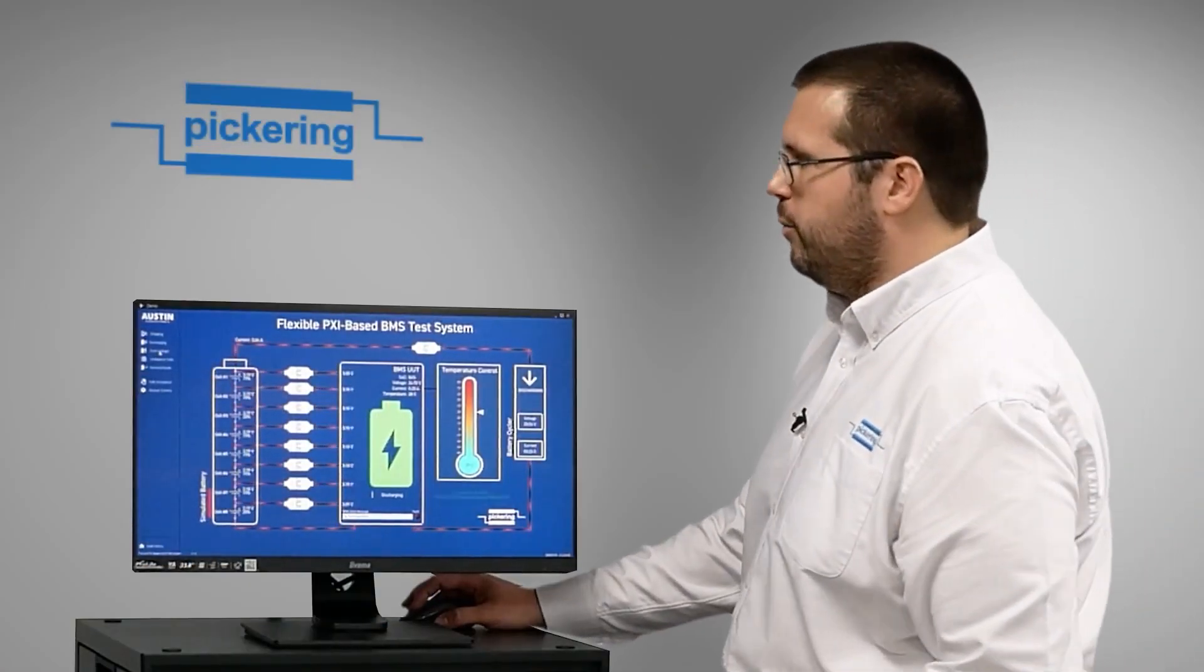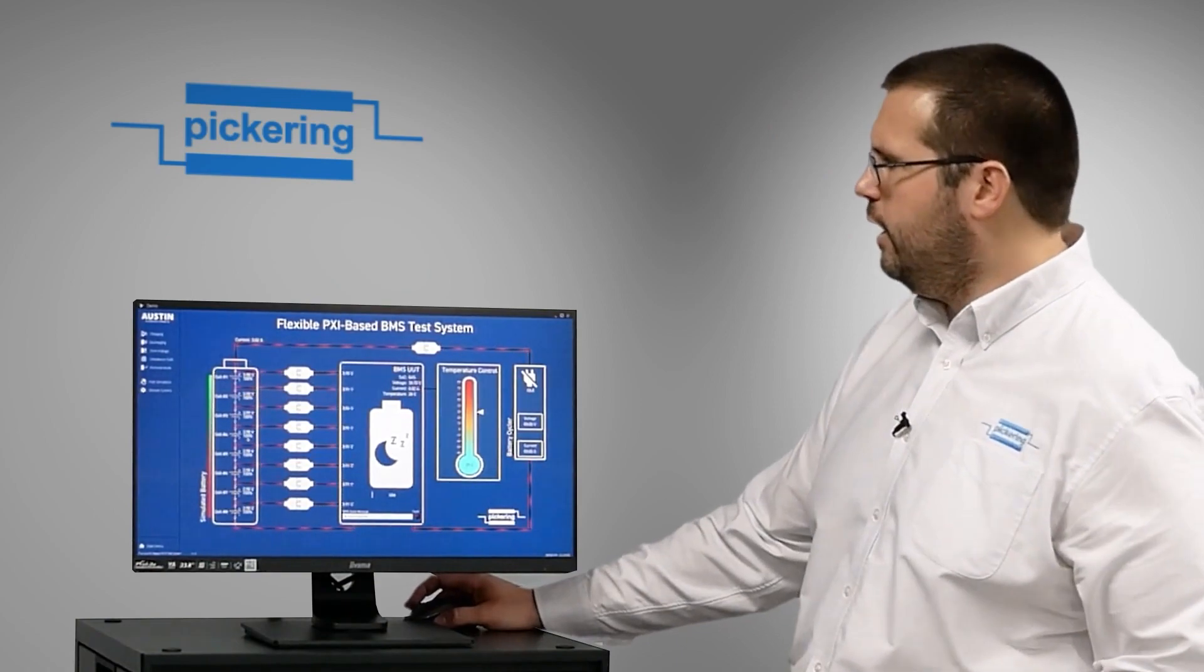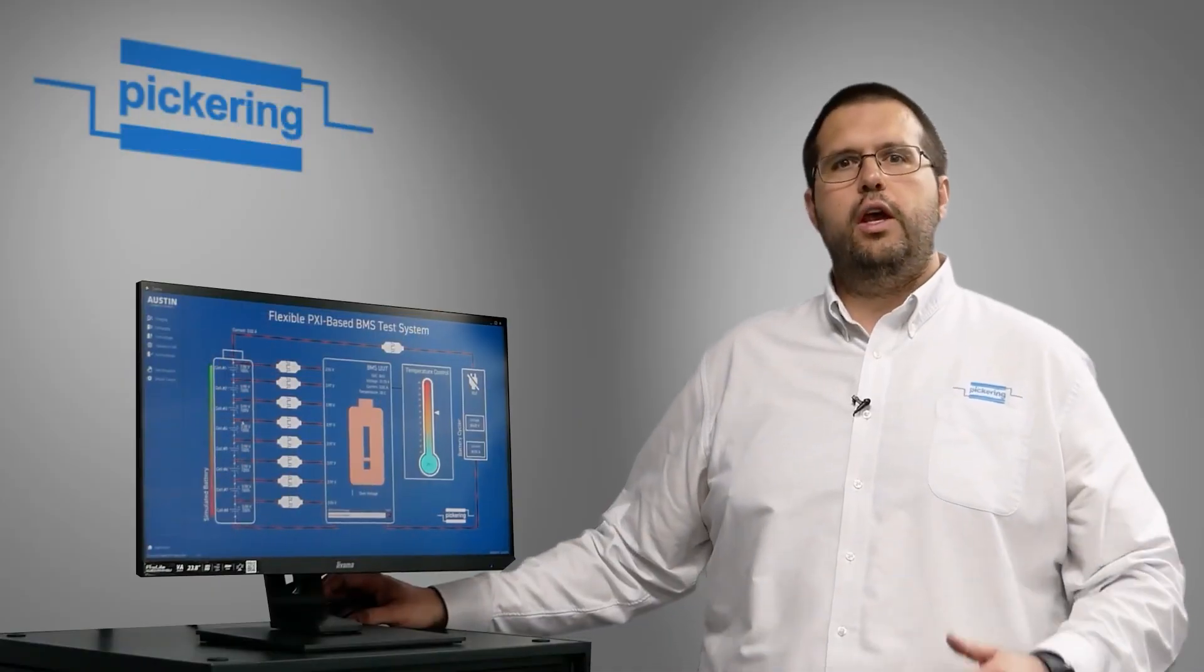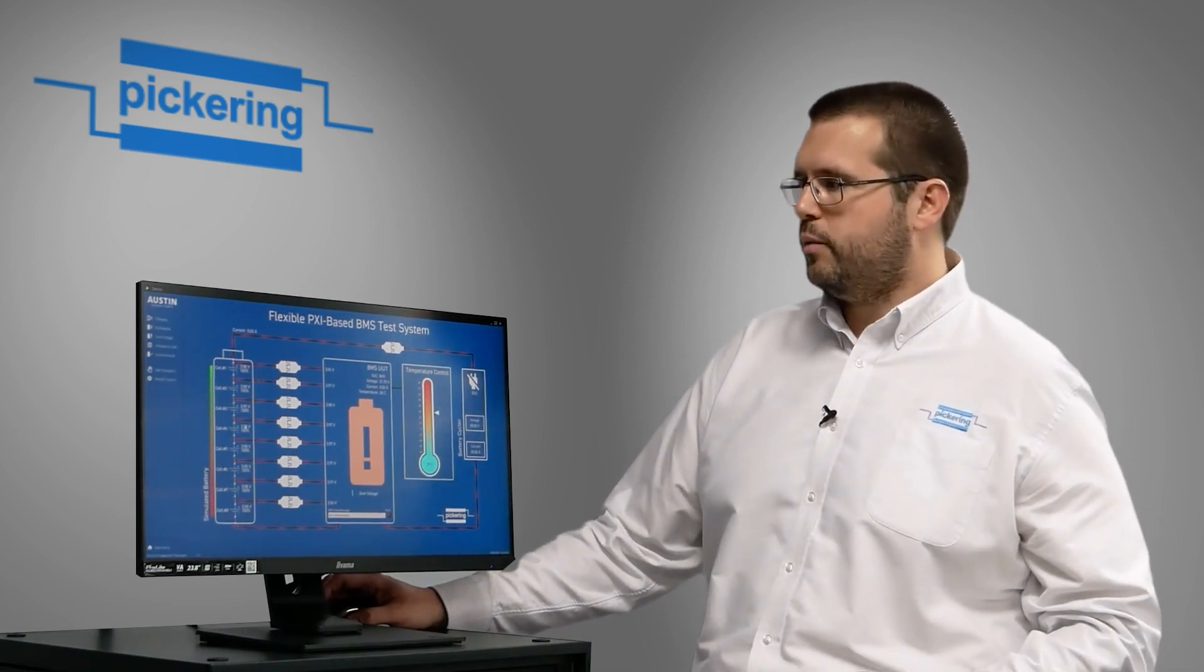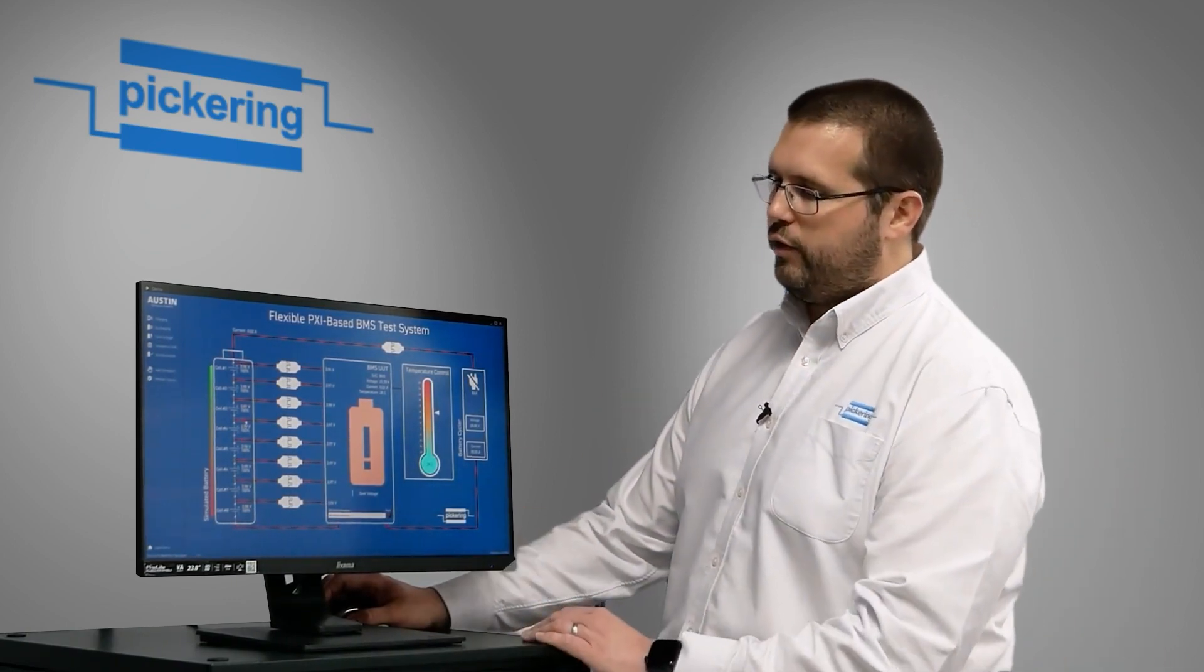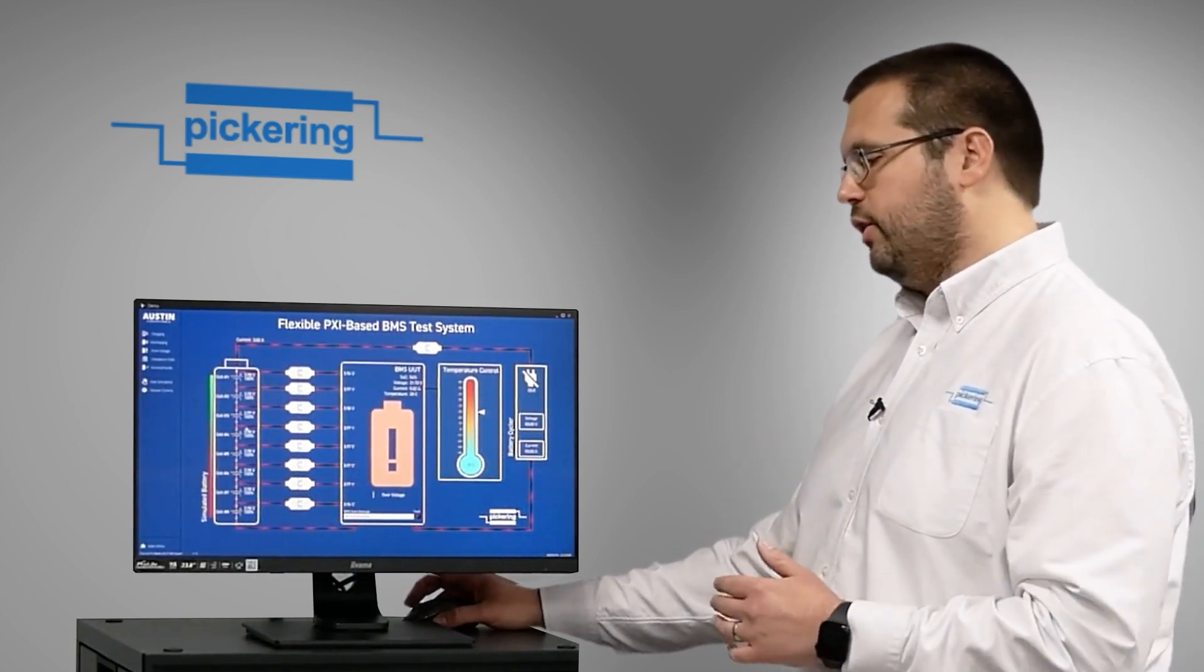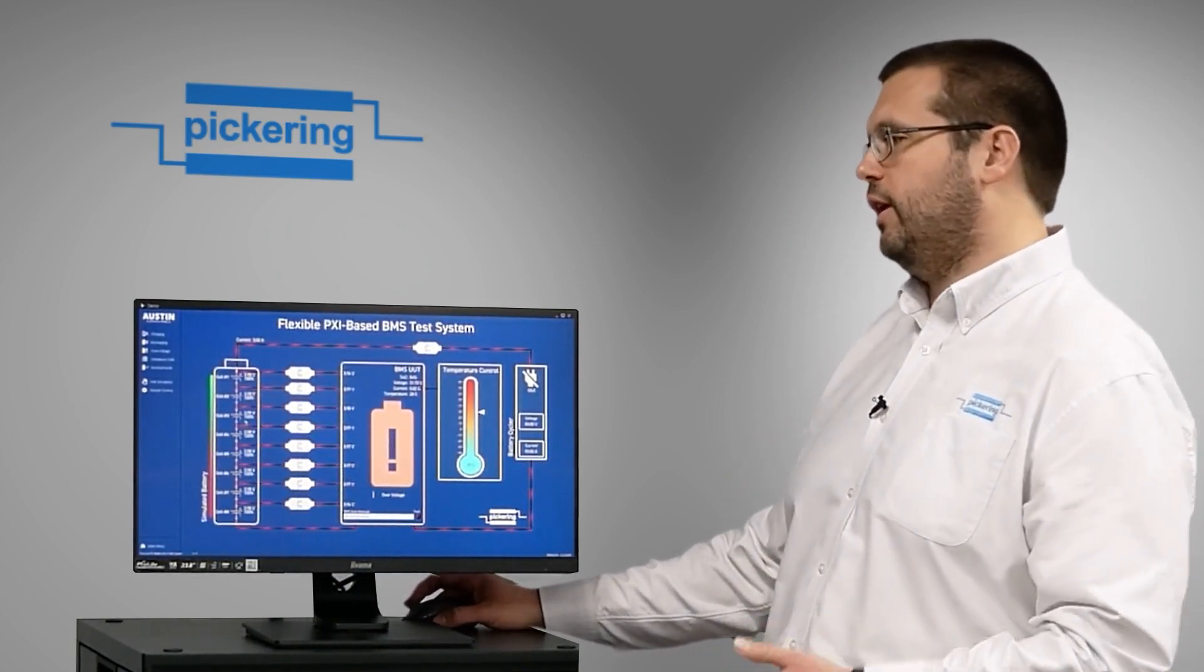Also we can simulate over voltage. On here all the cells are up to 3.98, 3.99 volts, which is obviously over voltage for a cell. Now the BMS has recognized this and it's returning a condition of over voltage, again showing that that functionality of this BMS is functioning as expected.